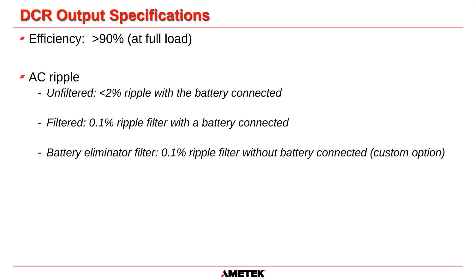So the theory of operation for the DCR battery charger is the AC input power is converted to a regulated DC output by an SCR charge bridge. The charger is a constant potential, phase-controlled 12 or 6 pulse solid state type with constant voltage and current control circuitry. All of our inputs are isolated with an isolation transformer, and an electrostatic shield is supplied for immunity against input disturbances and galvanic isolation to the DC loads. The operation of the system is insensitive to AC input phase rotation. And in the event of a power loss, upon restoration of the AC input power, the rectifier will automatically resume supply to the load.